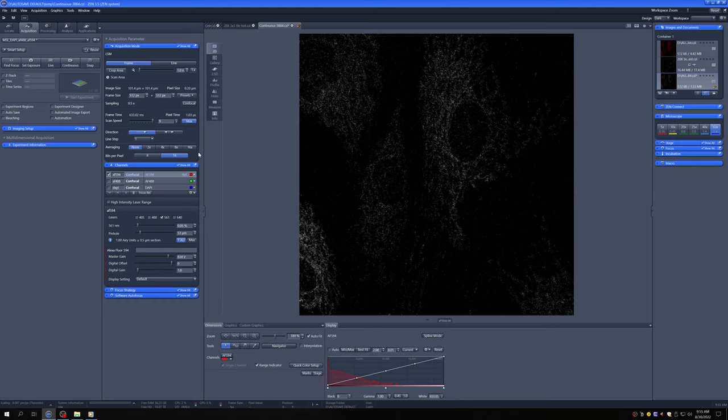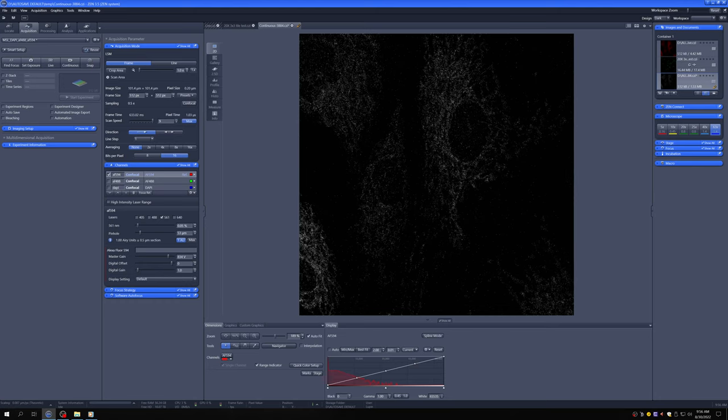You can see that averaging has two disadvantages, higher bleaching and that it will take longer. So then why would we ever do it? One is that even if you're delivering the same total amount of light, it ends up being the case that having the laser go by in one pass at very high power is more damaging than having the same amount of light but distributed over multiple passes. So if you really want to minimize bleaching, averaging is a good way of doing it.